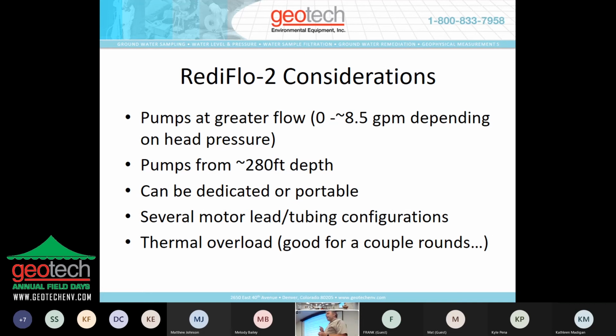So I want you to think about what that means in terms of sample integrity and the longevity of the pump, okay? When the thermal overload triggers, it's actually within the pump itself. It'll send a fault code to the controller. But most of us that are out in the field trying to get work done, the pump stops pumping, what do we do? We throw the circuit breaker and we start it up again because it shouldn't turn off. Shouldn't. It's a reliable overload, but it's only good for a couple of rounds because if that pump continually gets hot, that thermal overload fails and that pump turns into a paperweight in no time.